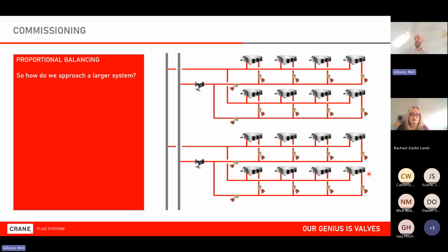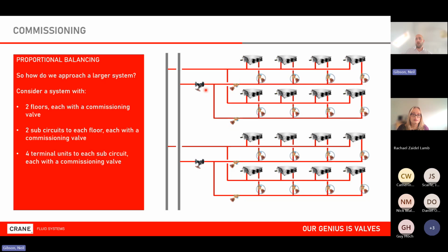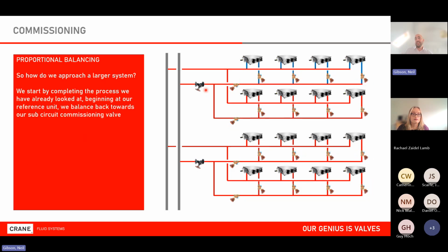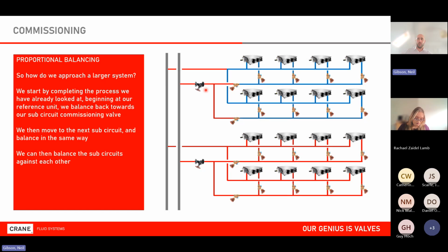Not only that, but when it comes to actually balancing the system and commissioning it, my 2-port valve can't do that. All it can do is be sized for the given flow rate and the pressure drop. It has no other intelligence built within it. So to balance my system, I still have to use these commissioning sets. And I typically have one on the floor, on a sub-branch, and on all of the individual terminal units as well. And some poor soul has to go around and individually balance all of these. They have to balance a branch, the next branch, 2 branches against one another, a floor, the 2 floors against one another. It's a laborious and time-consuming process.